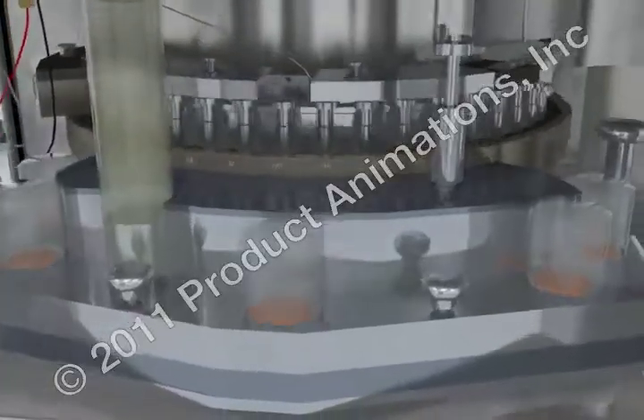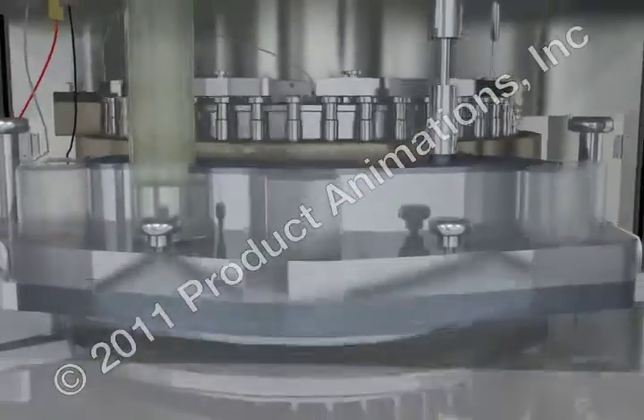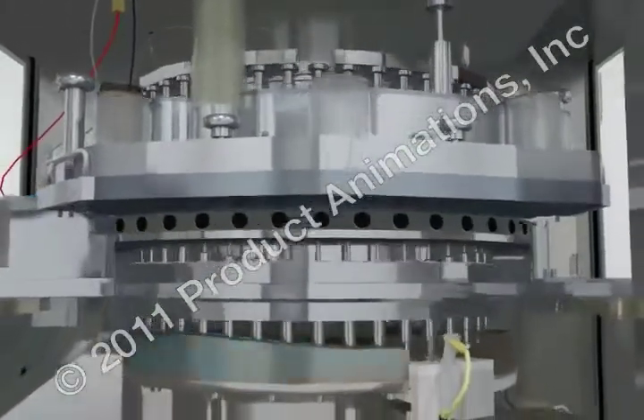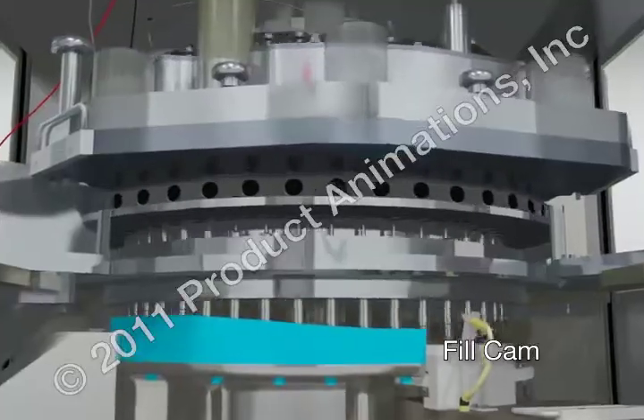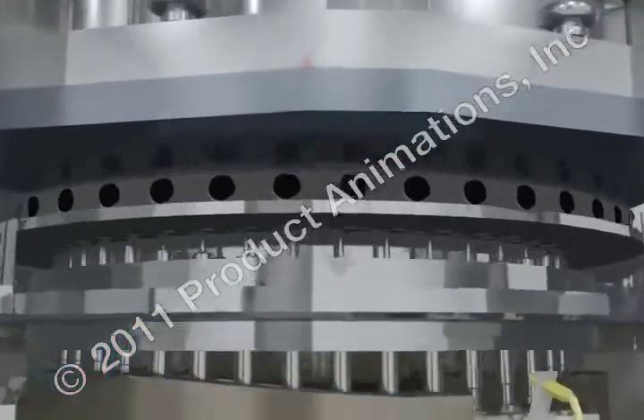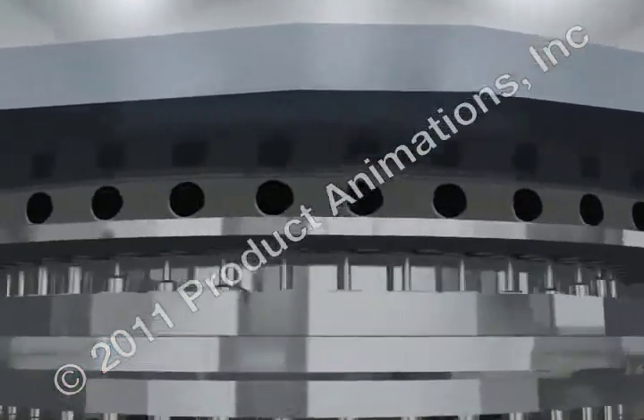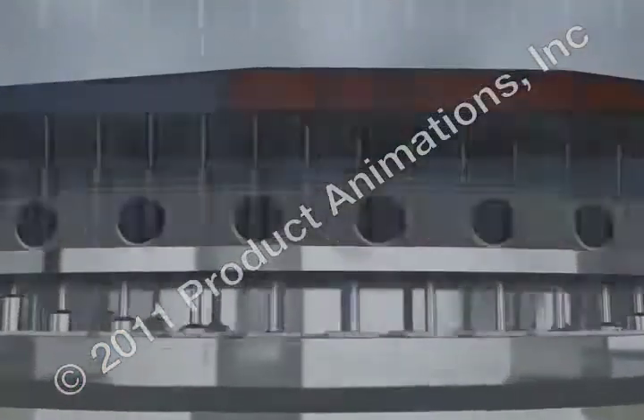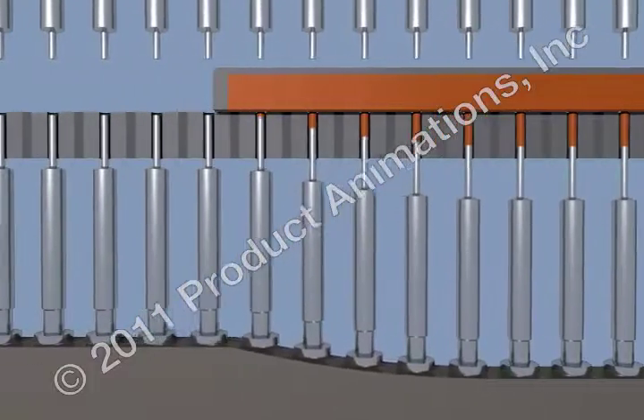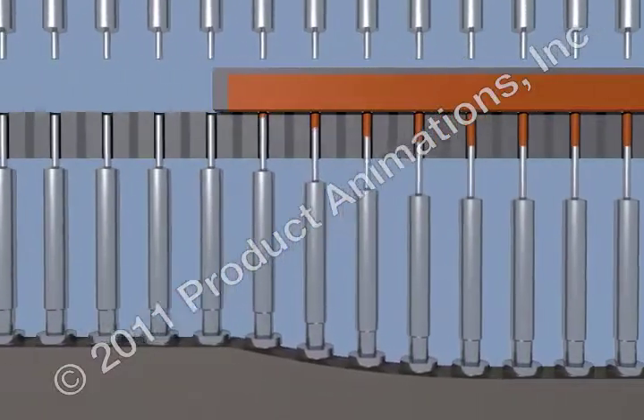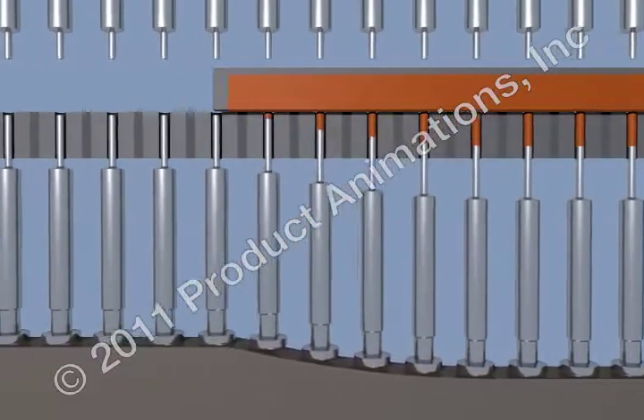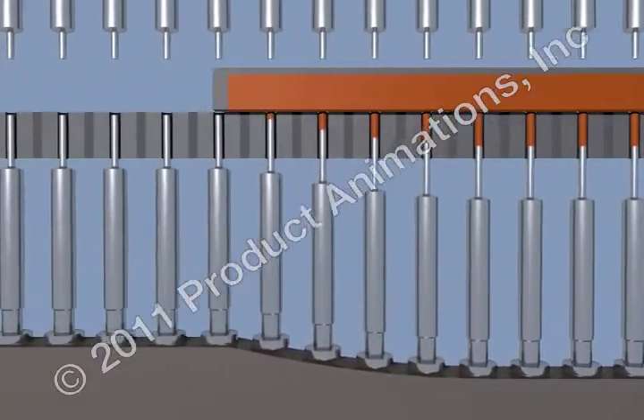As the turret is rotating, the lower punches are pulled down on the die by the fill cam when they pass under the feeder. This pull-down action causes the granulation in the feeder to be drawn into the die by the vacuum created.